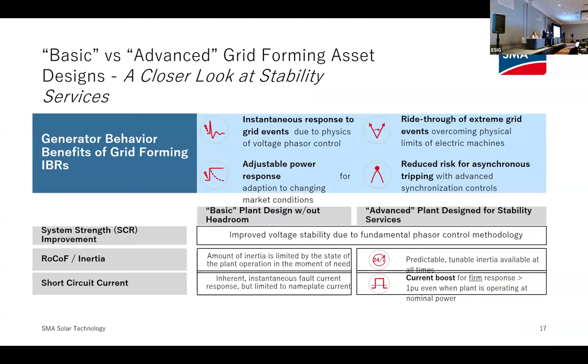Let me talk about what you get in a grid forming inverter all the time versus what you have to design for. The bar in blue at the top of the slide represents common behavioral benefits to the network with a grid forming inverter that are always there: instantaneous response to grid events — by nature of being a voltage-controlled converter, the reaction is not to a command but is instantaneous, it's the physics of being in voltage control mode. It's adaptable, adjustable, and tunable — it can be modified not just project by project but over the lifetime of a project. If you find that the need for inertia is increasing, you can adjust the parameters accordingly. You enable extreme ride-through capabilities, much more capable than a grid following inverter, thereby reducing the risk of tripping under adverse conditions.